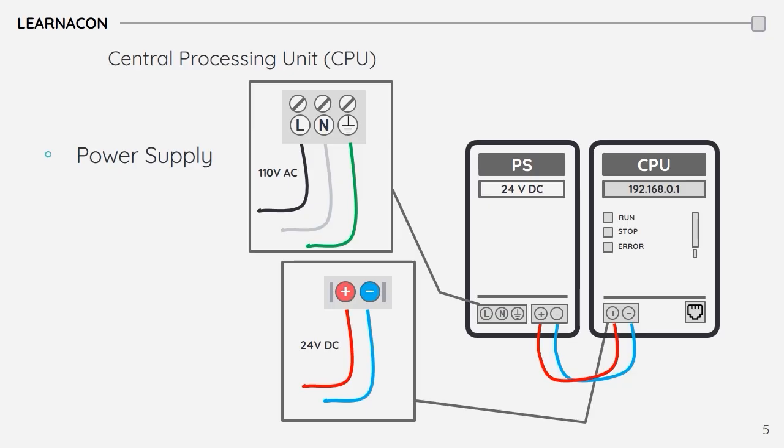Since the CPU is the most critical part of the PLC system and usually the most expensive piece, it is better to invest in a reliable power supply. Normally, the best option is the one that the PLC manufacturer offers. By default, all other PLC modules use a 24-volt DC power supply unless advised otherwise. Calculating the required power consumption and sizing a suitable power supply is part of the work you must consider in the PLC system design phase.